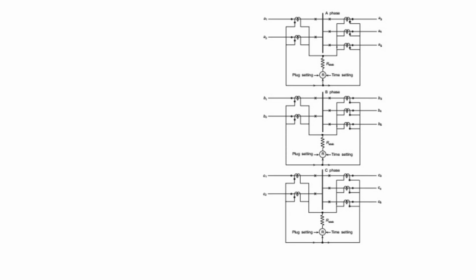In this lecture we have discussed busbars in single phase. All high voltage busbars are three phase, and we have considered only the single phase here. The figure shows a three phase busbar with 2 incoming and 3 outgoing lines. The protection scheme is simple and similar to that of the single phase that we have shown. Since we have used a stabilizing resistance here, this type of protection is known as the high impedance three phase busbar differential protection.